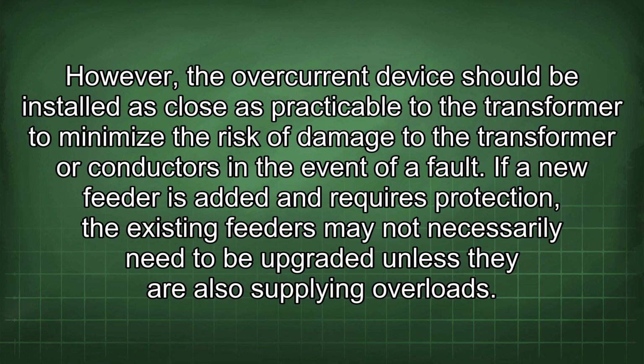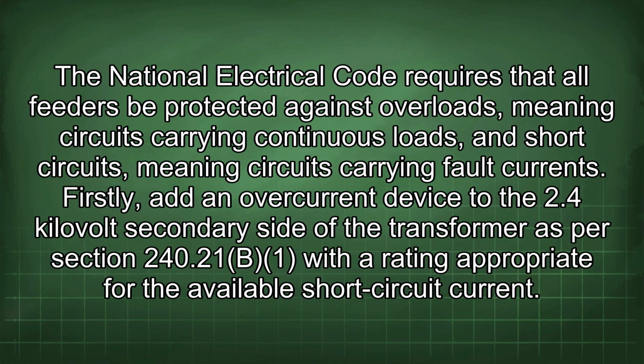However, the overcurrent device should be installed as close as practicable to the transformer to minimize the risk of damage to the transformer or conductors in the event of a fault. If a new feeder is added and requires protection, the existing feeders may not necessarily need to be upgraded unless they are also supplying overloads. The National Electrical Code requires that all feeders be protected against overloads, meaning circuits carrying continuous loads, and short circuits, meaning circuits carrying fault currents.